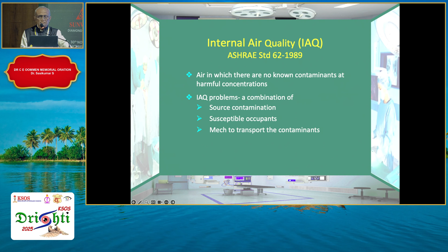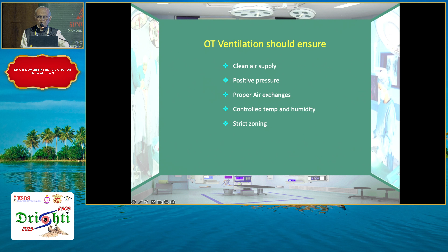OTs come under ISO class 6 or class 1000, where the permitted number of particles of 0.5 micron size at rest is 1000. Proper ventilation should ensure clean, cool, dehumidified air under positive pressure with adequate air exchange and fresh air intake, helping to maintain the zoning in the OT. And zoning is important to minimize the risk of hospital infection, and to minimize the unproductive movement of staff, supplies, and patients. It increases the optimum utilization of staff and other facilities to ensure a smooth workflow.